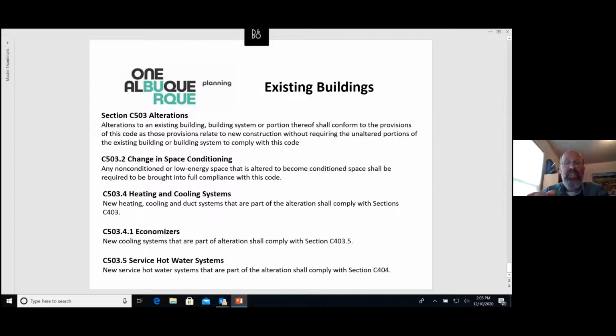If you're changing the space conditioning and you had a space that had no conditioning in it, or, excuse me, a low energy space, that is now going to become a conditioned portion of this space, then that has to be brought up to the code. Again, with the heating and cooling systems, same thing. Economizers would need to be addressed on the altered portions. The existing portions, not so much.